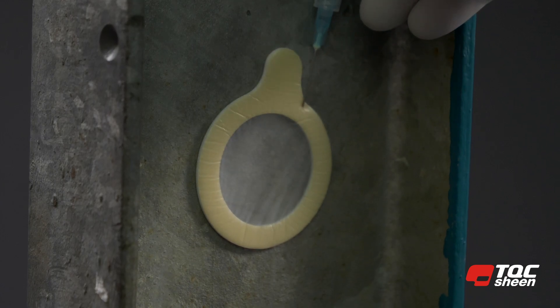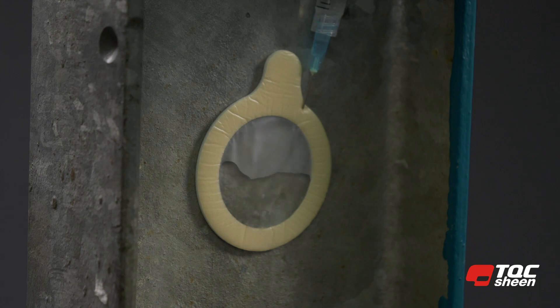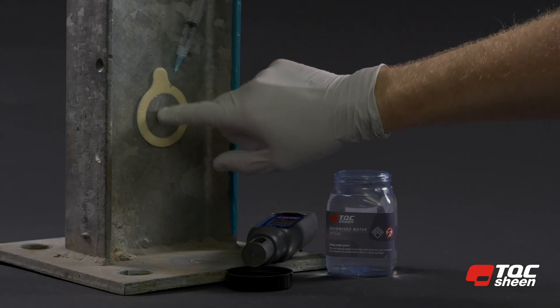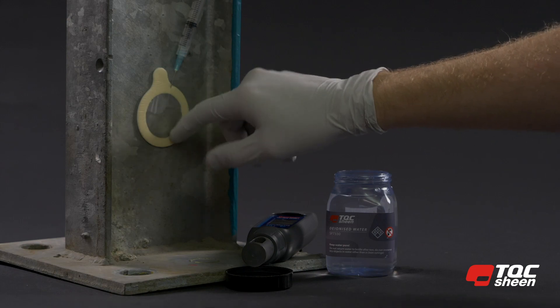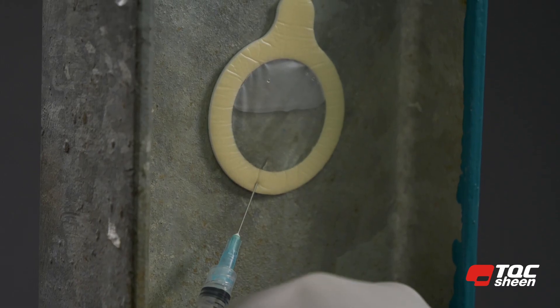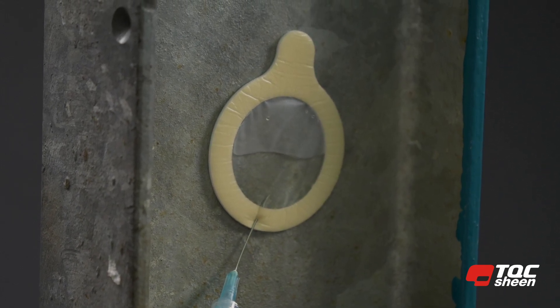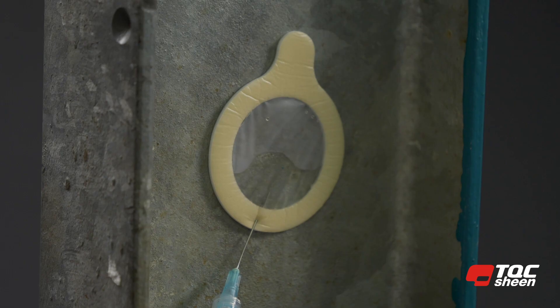Inject the demineralized water into the Bresle patch through the membrane and foam edge at an angle of approximately 30 degrees. Tap the Bresle patch membrane for 90 seconds to distribute the demineralized water. Repeat the procedure of inserting and removing the demineralized water four times.